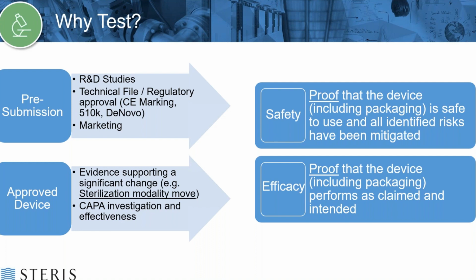And then after you have an approved device, you might do some testing to support a change. If you change a sterilization modality or if you change your packaging configuration, you're probably going to need to go back and repeat some of that testing to be able to submit again to any regulatory bodies to show that change hasn't significantly impacted your product's ability to function and stay sterile the way it should. Also, to support CAPA investigations or anything like that, you might need to do some additional testing.